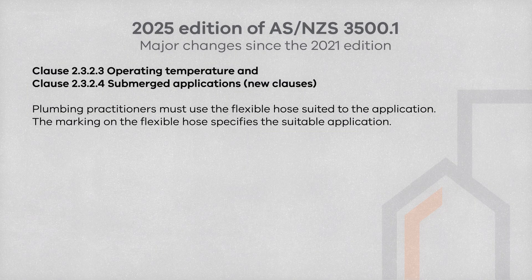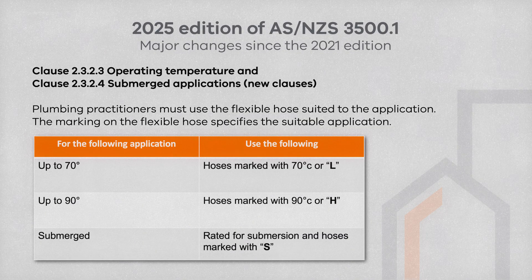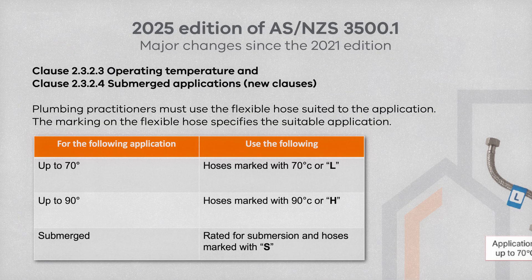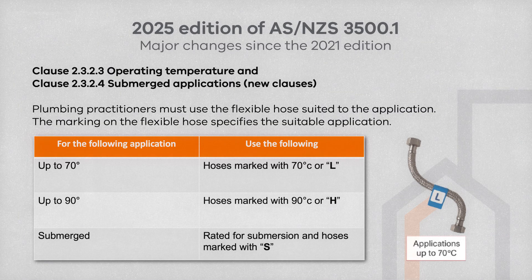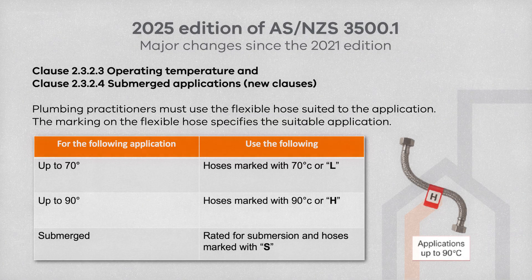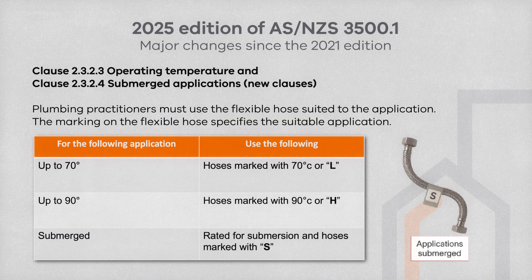There is a new Clause 2.3.2.3 regarding the operational temperature range of flexible hose assemblies, also covering applications where the hose may be submerged. You must only use a hose assembly rated for its intended application. For hoses rated for applications up to 70 degrees Celsius, they are marked with '70°C' or the letter 'L'. For hoses rated up to 90 degrees Celsius, they are marked with '90°C' or the letter 'H'. In submerged applications, hoses must be rated for submersion and marked with the letter 'S'. Hoses marked with S may have a protective external coating or additional resistance to corrosion.